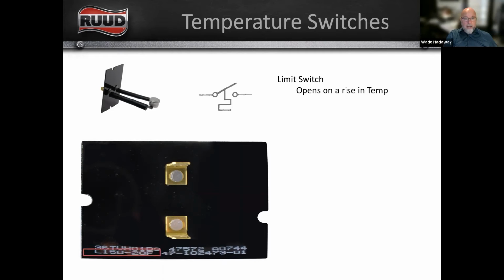One thing that I want to point out on these limit switches is that on the outside of the switch itself, it lists the temperature that the switch will open at, and then how much it has to cool off before that switch will close. So for this example, that switch is going to open at 150 degrees, and then that 20F next to it indicates that it has to cool off 20 degrees before it'll close again. So from looking at this, we know that switch will open at 150 degrees and that it'll close again at 130 degrees Fahrenheit.